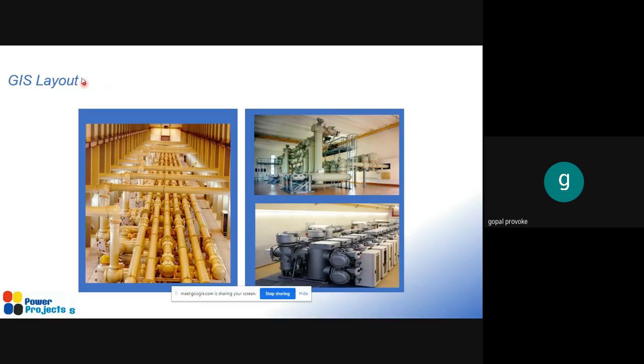And we have a GIS substation, or a gas insulated substation. In a gas insulated substation, the phase conductors, or the current carrying conductors, will be placed inside a medium which has a gas. For example, if you see here, we have two RYB. There are 6 conductors: RYB, and again RYB. So totally there are 6 conductors, two 3-phase systems, and this is a cylindrical pipe, or a cylindrical tube, and in the middle of this tube the conductors will be placed, and this tube will contain gas, which is SF6, or sulfur hexafluoride.